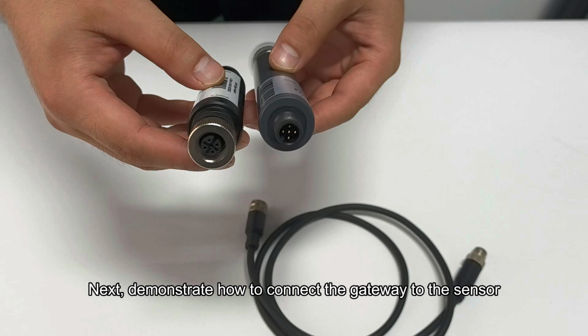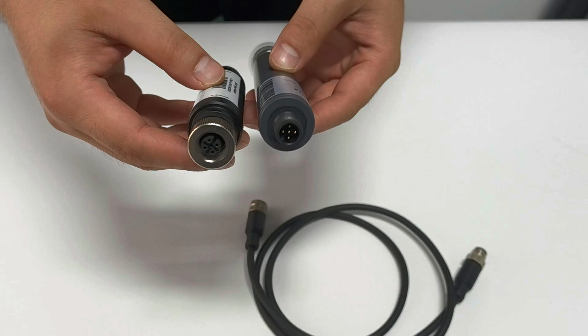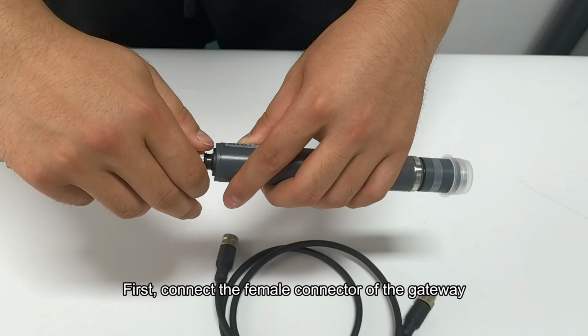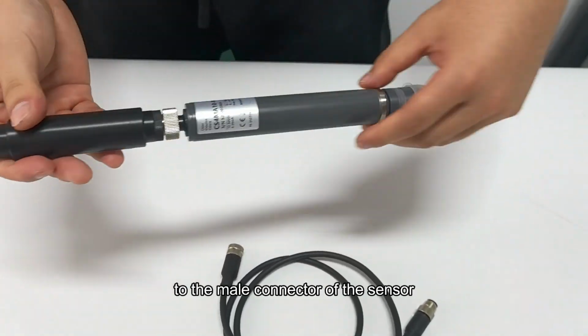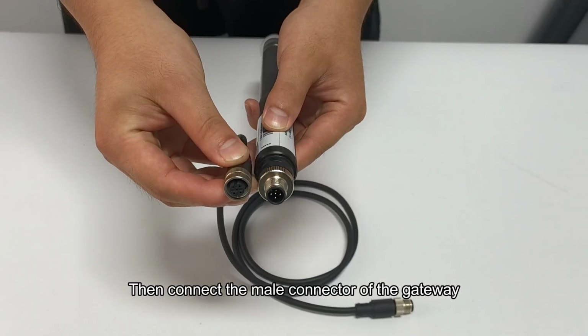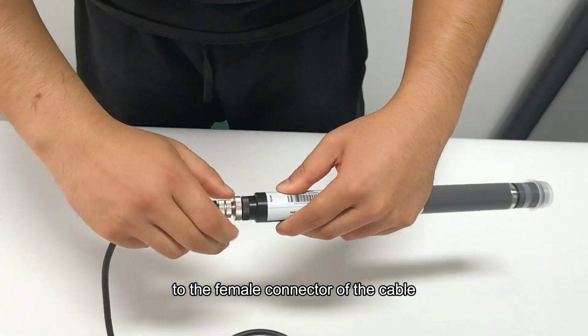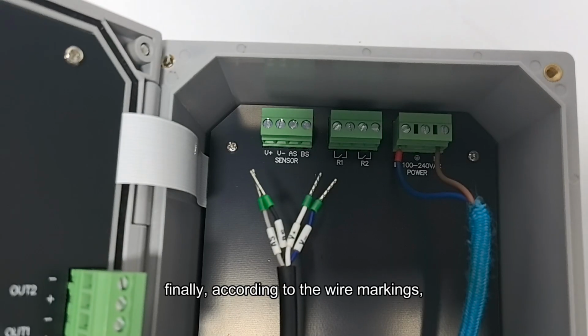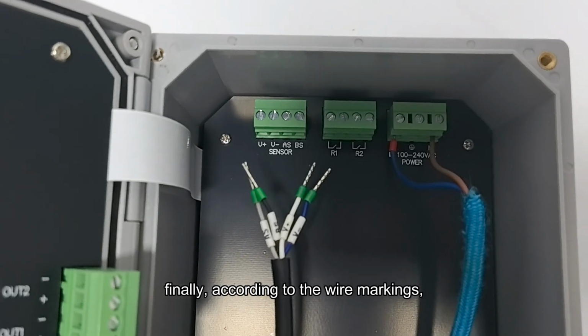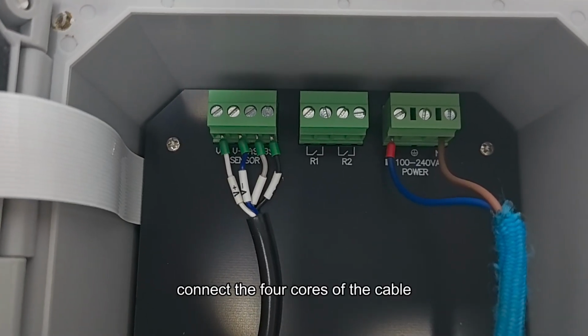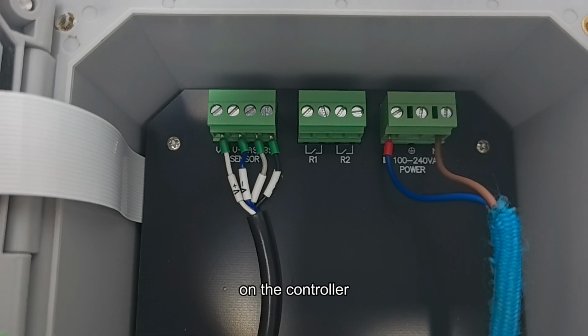Next, we demonstrate how to connect the gateway to the sensor. First, connect the female connector of the gateway to the male connector of the sensor. Then connect the male connector of the gateway to the female connector of the cable. Finally, according to the wire markings, connect the 4 cores of the cable to the corresponding terminals on the controller.